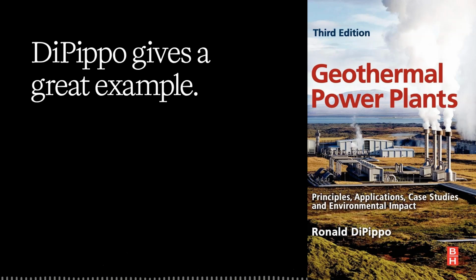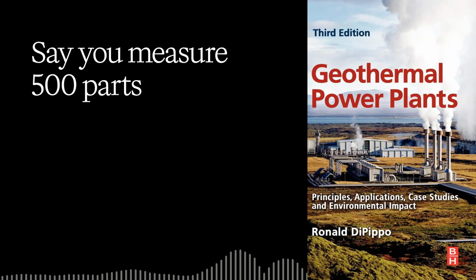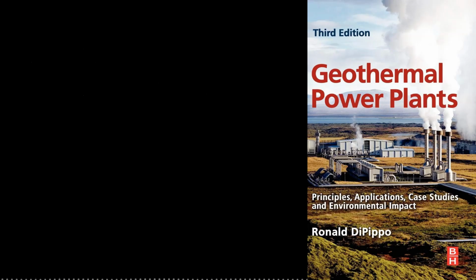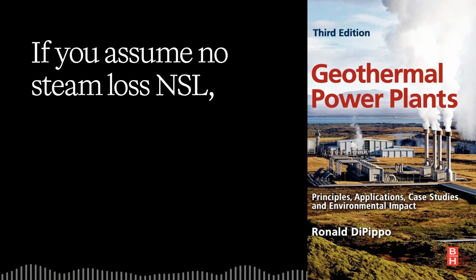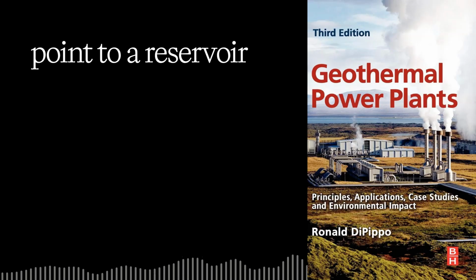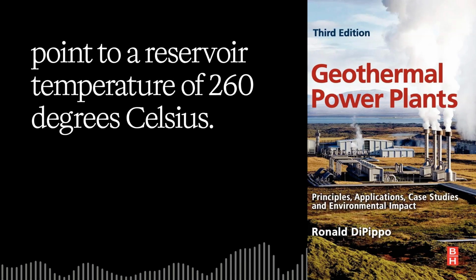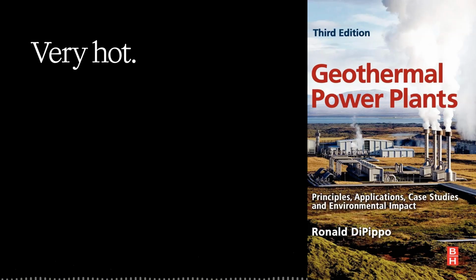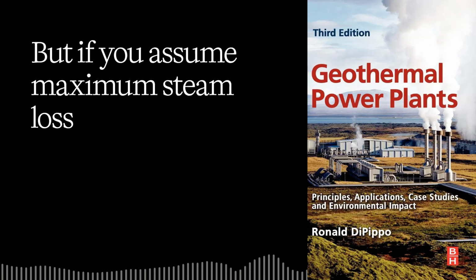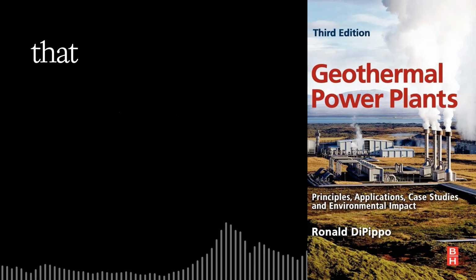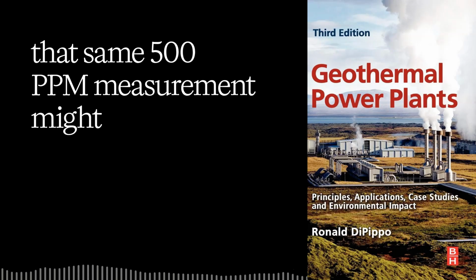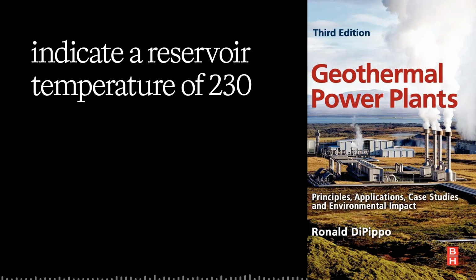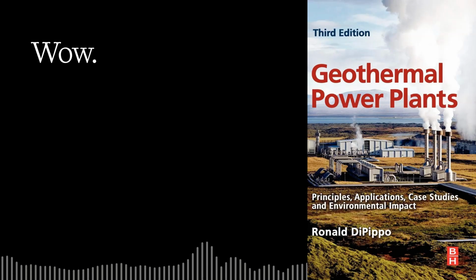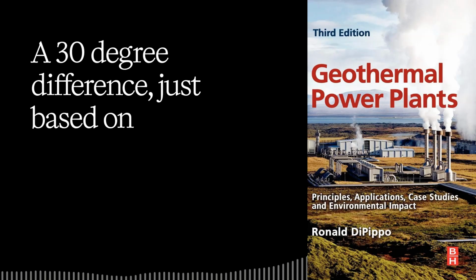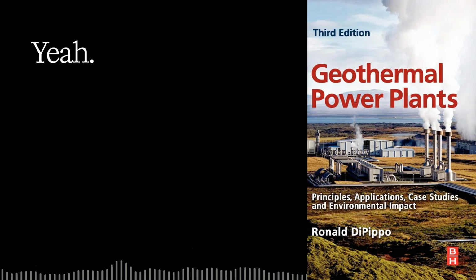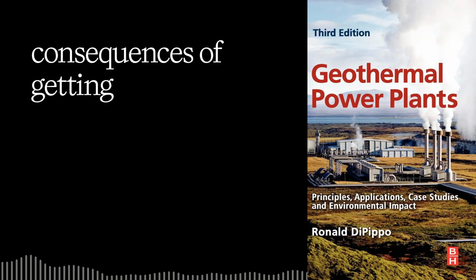DiPippo gives a great example. Say you measure 500 parts per million of silica in your sample. If you assume no steam loss, NSL, the calculation might point to a reservoir temperature of 260 degrees Celsius. Pretty hot. Very hot. But if you assume maximum steam loss, MSL, occurred, that same 500 ppm measurement might only indicate a reservoir temperature of 230 degrees Celsius. Wow, a 30-degree difference just based on an assumption about steam. That's huge. What are the practical consequences of getting that wrong?